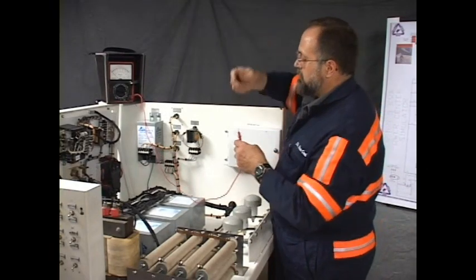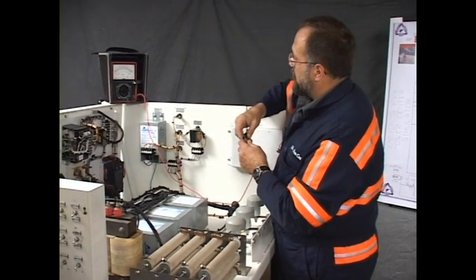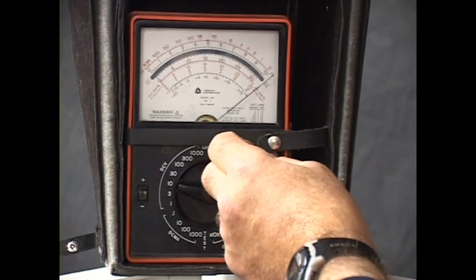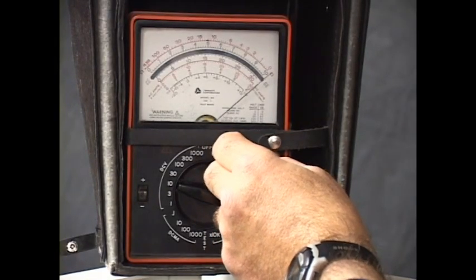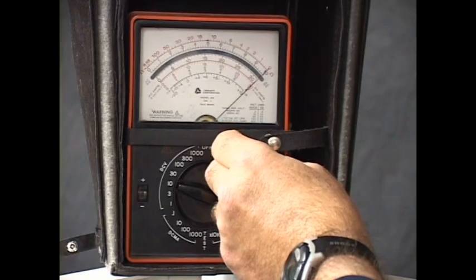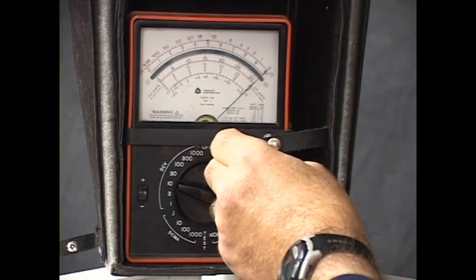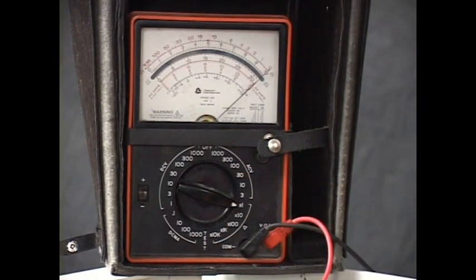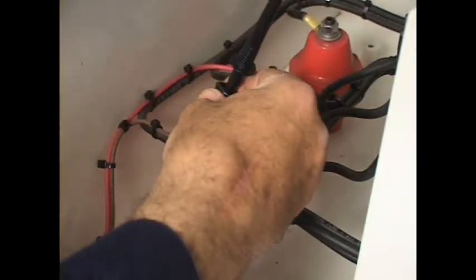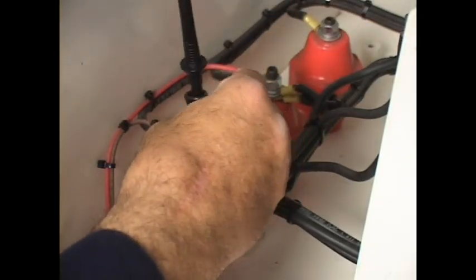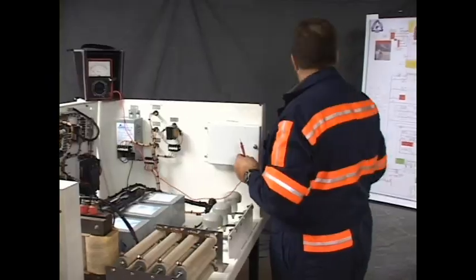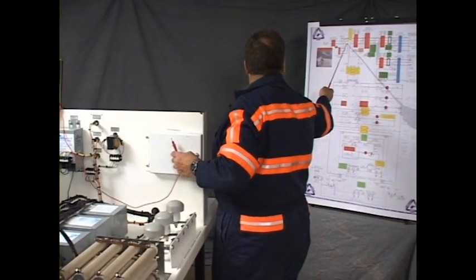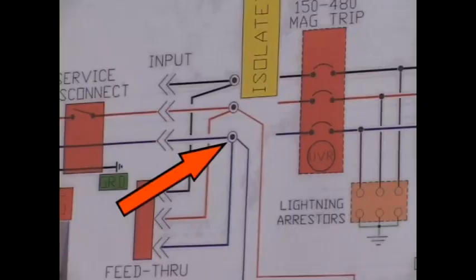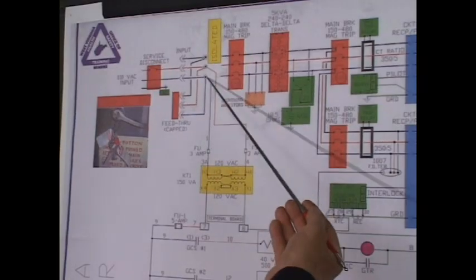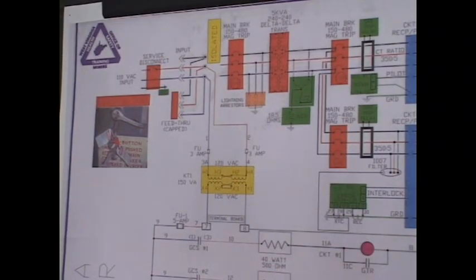I should zero this instrument first. To get an accurate reading, you have to adjust the instrument until it actually reads 0 when the leads are shunted together. I'm going to attach one probe to the number 1 wire where it originates on the print. That would be here. And just as if I were following a map, I'm going to go to the other end of the wire, which is on a fuse, FU1.